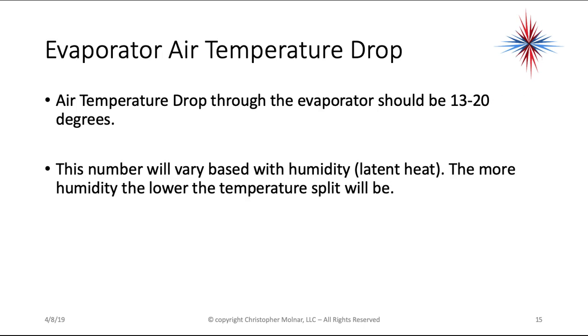Evaporator air temperature drop — your delta T temperature split — should be between 13 and 20 degrees. This number will vary based on humidity. The more humidity, the lower the temperature split will be, because a lot of the cooling power is going to remove that humidity from the system. Temperature drop through the evaporator: 13 to 20 degrees. For higher efficiency equipment you may see different numbers, but again, this is a rule of thumb.